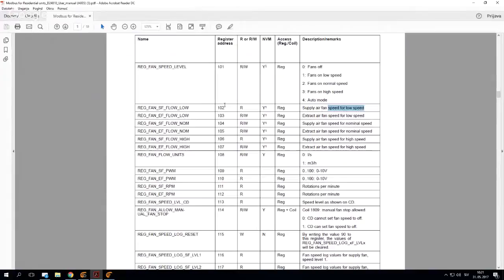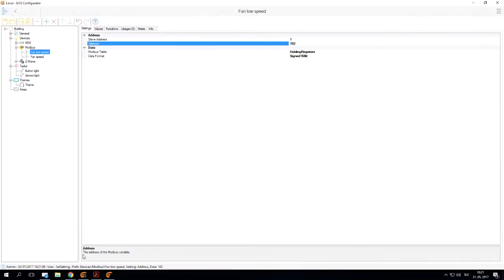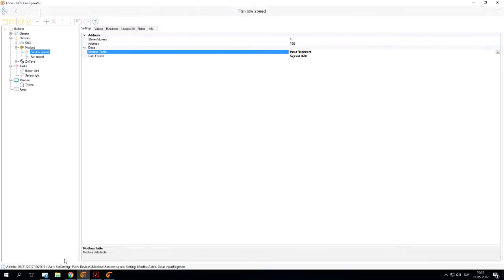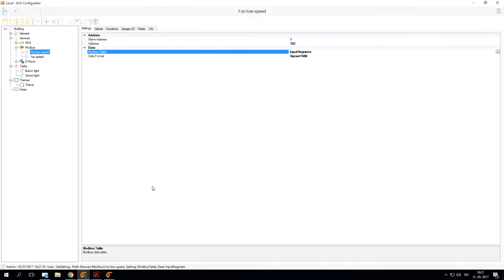I'm going to add another integer, fan low speed. Let's see that the address is 102. We change the address here to 102. Now we can see that this address has only a read value here, so we need to change our Modbus table from holding to input registers. And that is basically it, how to control this fan at low speed address. As simple as that.